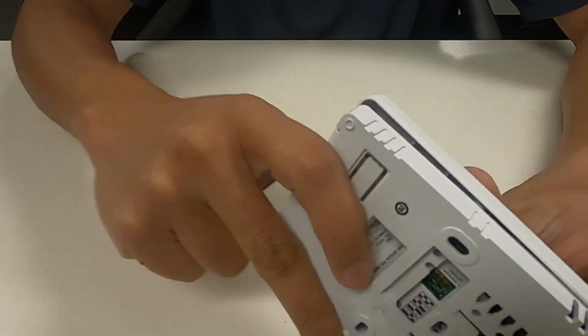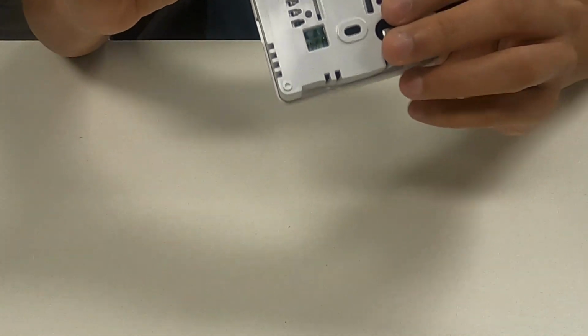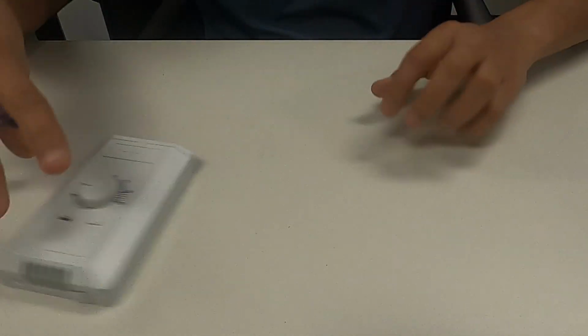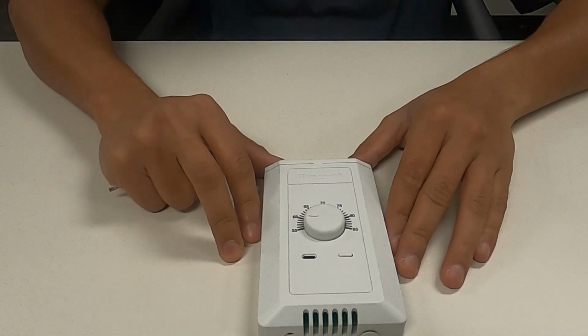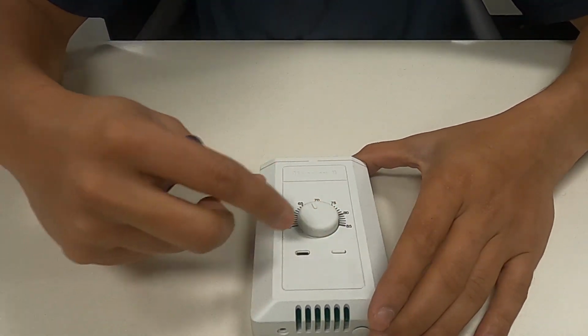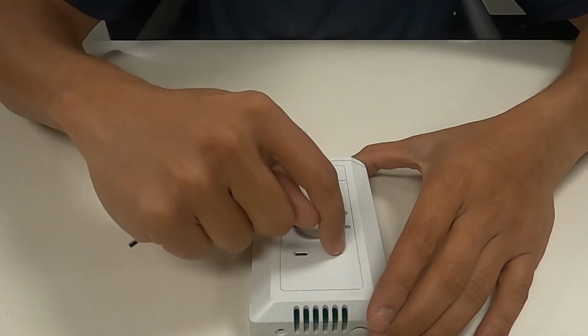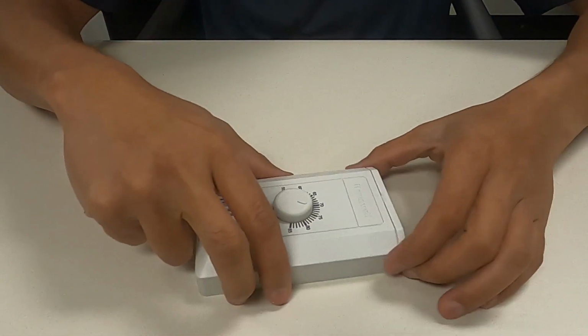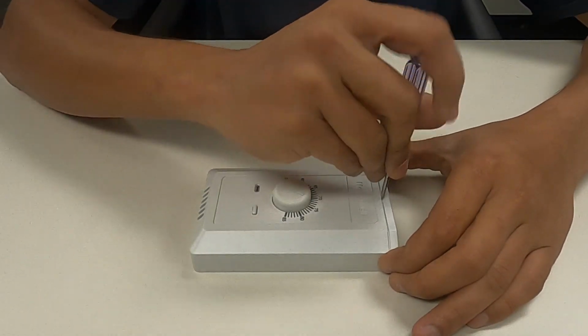So it can be either on the duct, depending on the duct size, or in the unit, based on what applications you're using this with. Based on how much the duct length is, you might have to appropriately consider the length of the temperature probe which you're inserting.